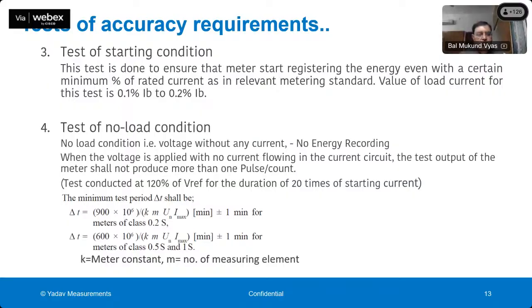Another test, as I told you, is the test of no load condition. When there is no load connected to the meter and no current is passing through the meter, the meter should not register any energy. That is the requirement, and the time for which the test engineer has to wait to check whether the meter has registered energy has to be calculated as per the formulas given on this screen. There are two different formulas, and this time comes out different for different current ratings and voltage ratings. Sometimes it can be 15 minutes, sometimes you have to test for 45 minutes or so.